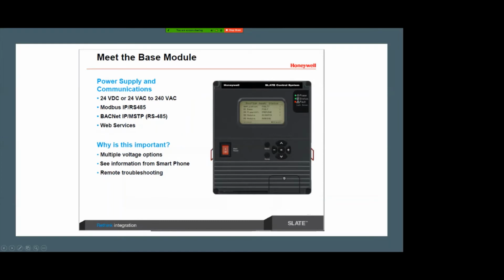So one really cool feature with our base unit: look at the voltage requirements for this module, 24 volt DC to 24 volt AC, up to 240 volt AC. Universal power, so a very flexible unit from power requirements. I mentioned before we've got the Modbus and BACnet ports, communication ports native to this base.